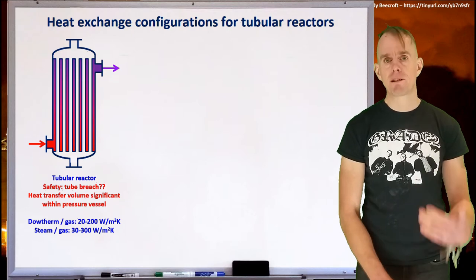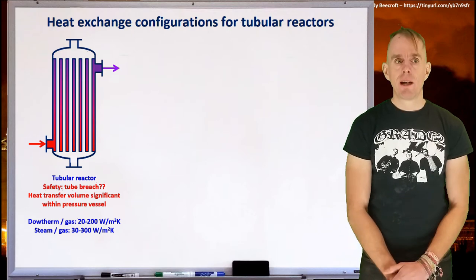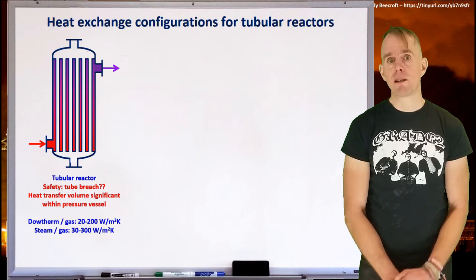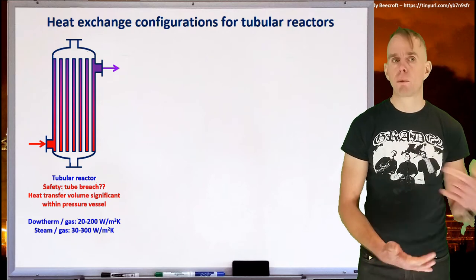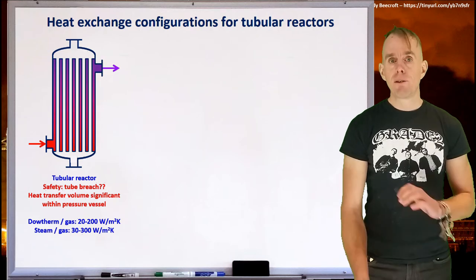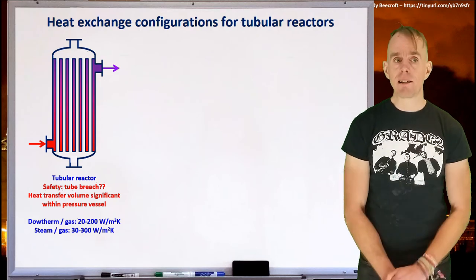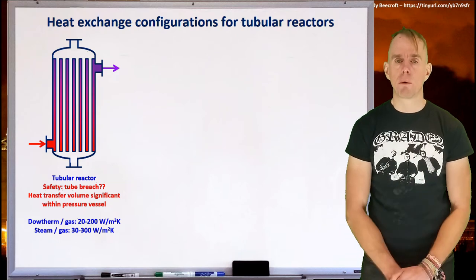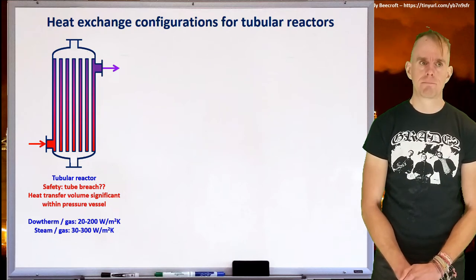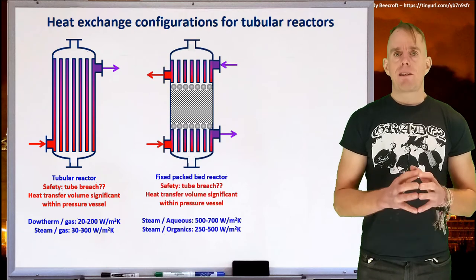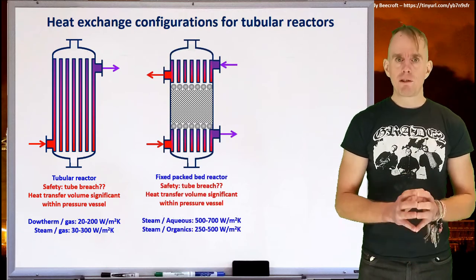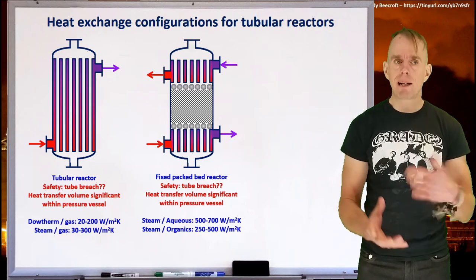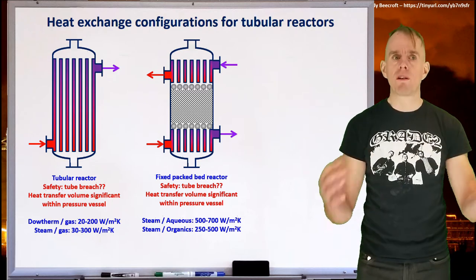So if we're thinking about the heat transfer coefficients that can be achieved, if you're using Dowtherm heating a gas, then you might achieve somewhere in the window of 20 to 200 watts per square meter Kelvin. If you're using steam heating a gas, it's kind of similar, somewhere in the window of 30 to 300 watts per square meter Kelvin. If you think back to the ammonia example, we saw that what we had was an integrated system where we had packed beds and tube bundles all in the same pressure vessel.